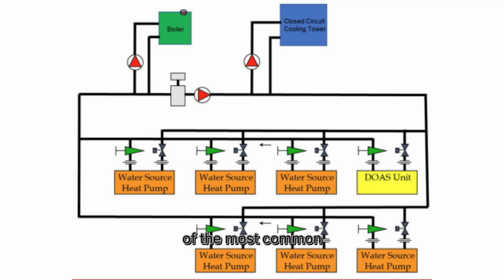Let's talk about one of the most common challenges in WSHP design: humidity control. On humid, mild temperature days, water source heat pumps often cycle off quickly. That's because the thermostat only senses temperature, or the sensible load, not the humidity, which is the latent load. The result? High indoor relative humidity, creating that clammy, uncomfortable feeling, even when the temperature looks fine on the thermostat.